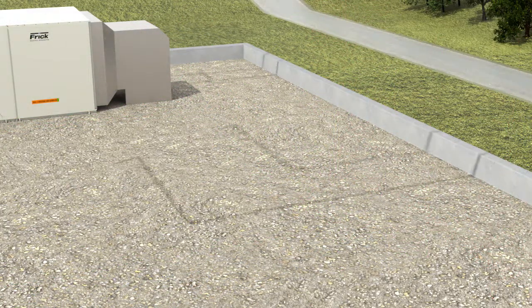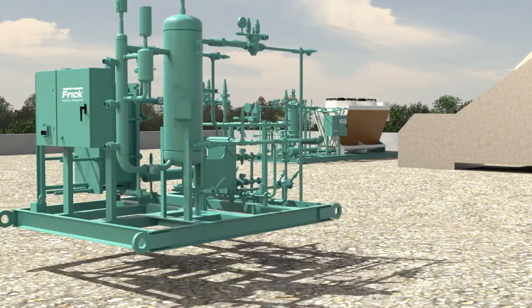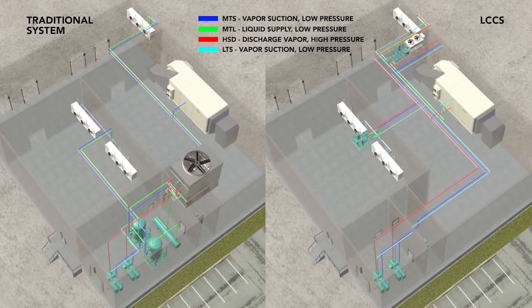The Frick low-charge central system minimizes the liquid ammonia through the use of remote distributed condensers, with the choice of adiabatic, plate-and-frame, dry, or evaporative. The liquid ammonia is located in very close proximity to only where it is needed, at the localized condensers and evaporators, away from the engine room. The modular nature of this system allows greater flexibility in design and installation.